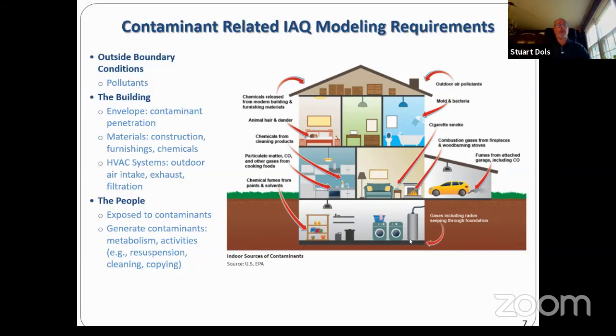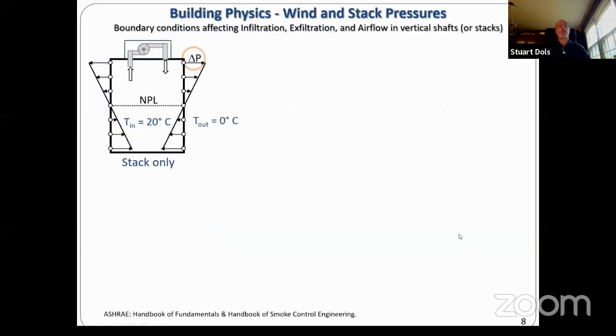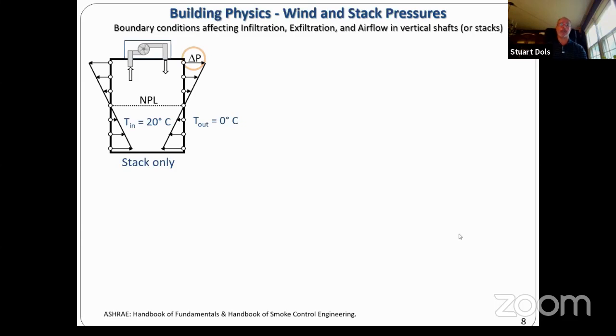To understand the effect of these boundary conditions on infiltration and airflow in vertical shafts, we need to talk about building physics. This simplified elevation model shows a building with no internal resistance to airflow and uniformly distributed leakage. With cold outdoor air more dense than warm inside air, differences in density lead to pressure differences across the building envelope. Pressures at the bottom of the building are lower than outside at the same elevation, so air flows in at the bottom. The opposite happens at the top. Somewhere in the middle is the neutral pressure level, where there is no airflow in or out.